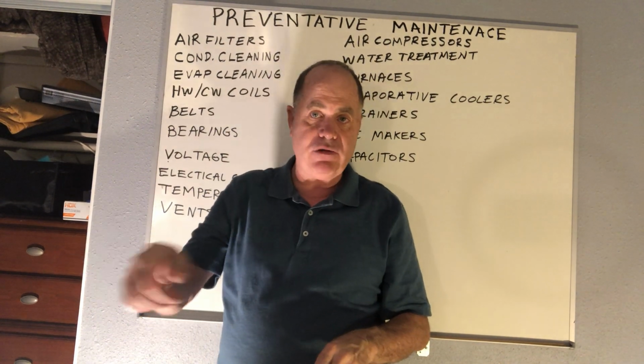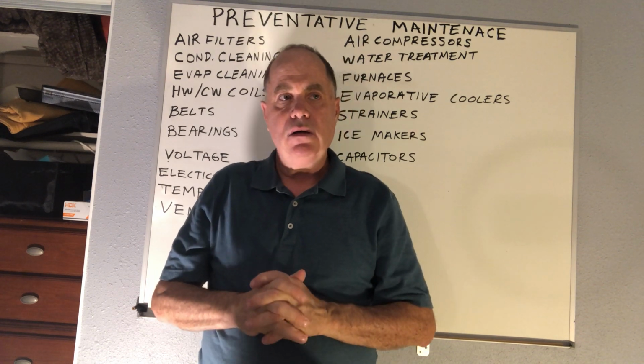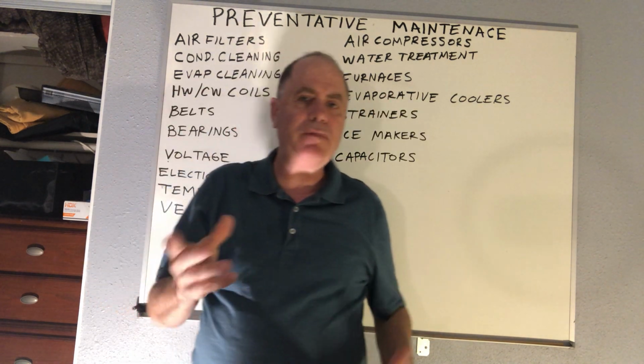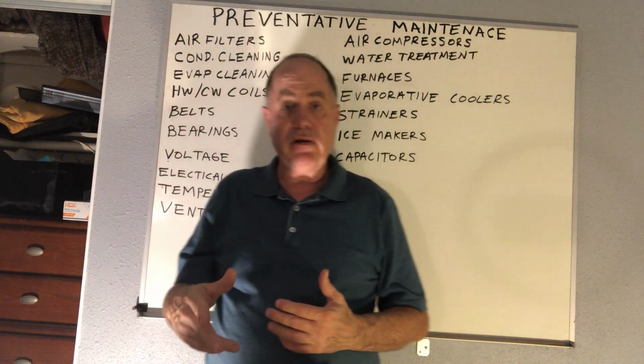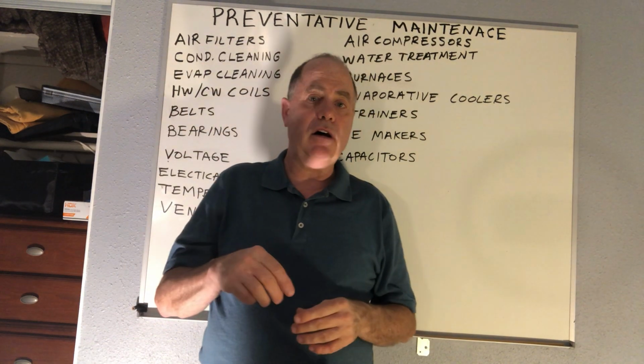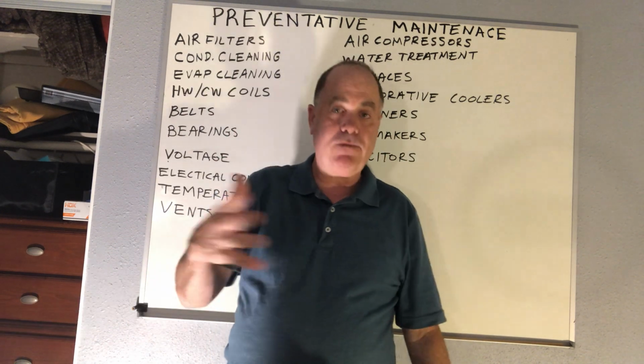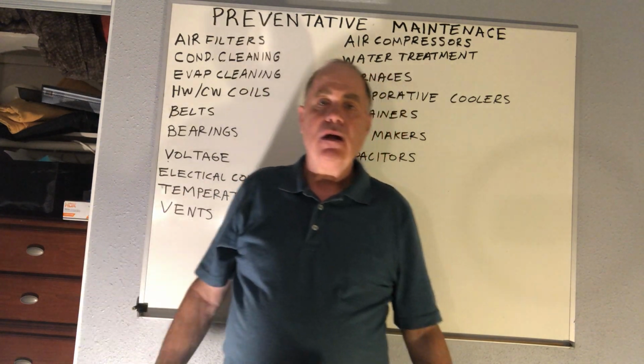This is where you shut off the refrigeration and just hit the pump button or the clean button on your control board for your ice maker. Then it circulates the water, and you have something like a bleach solution that will kill bacteria, fungus, or protozoa in the water. Then you flush that out, drain it down, refill it, run the pump again a little bit more, and flush that out before you refill it. Don't mix that chemical with cleaner, okay?